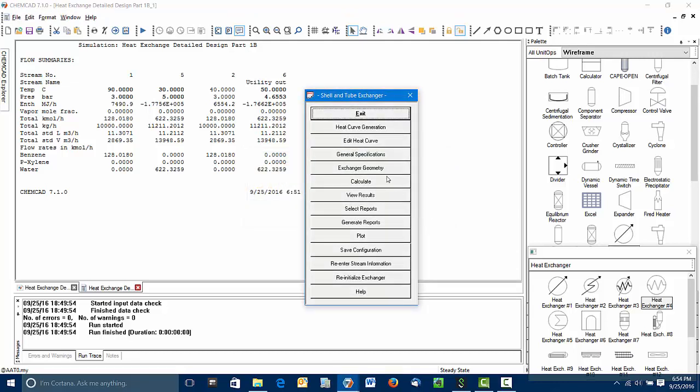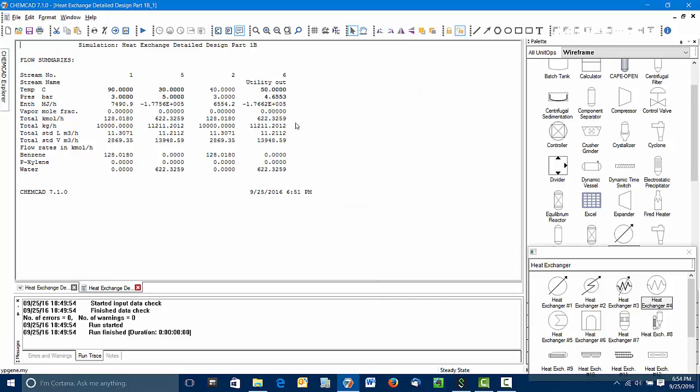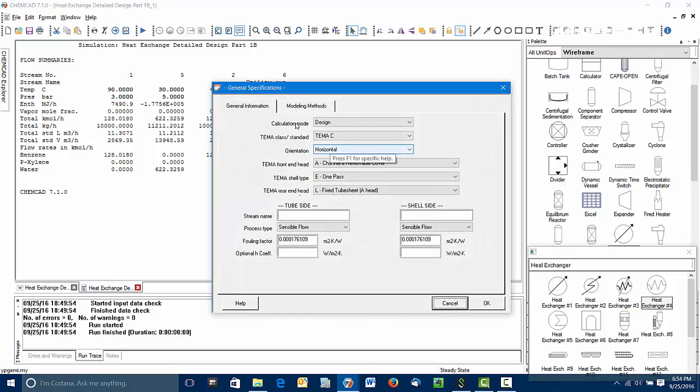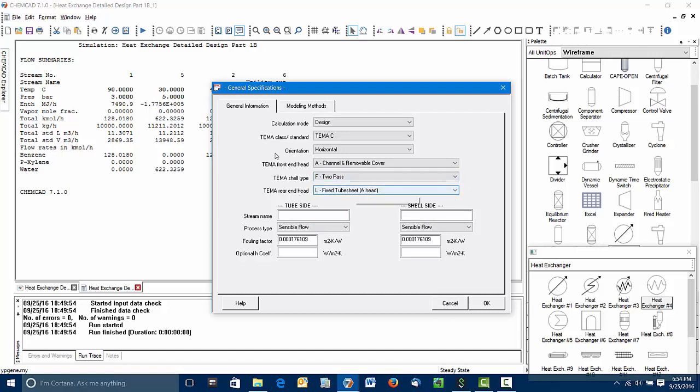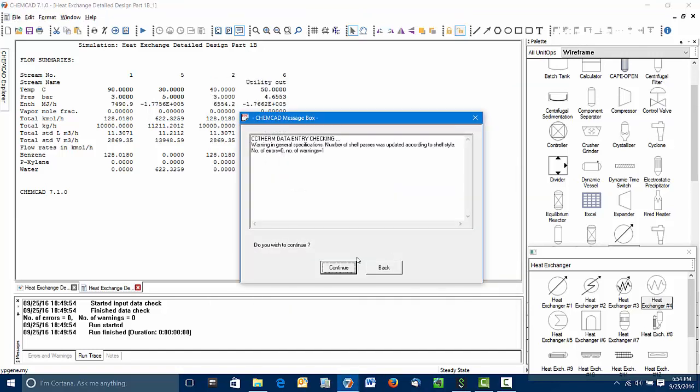What we can do for now is go into the general specifications. The shell side velocity was too slow. That means one of the first things we should try would be going from one pass on the shell side to two passes on the shell side. That will also double the number of tube passes.